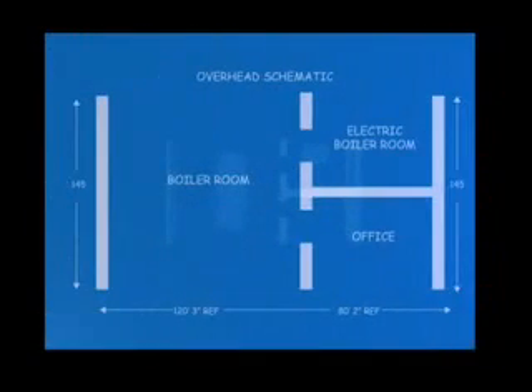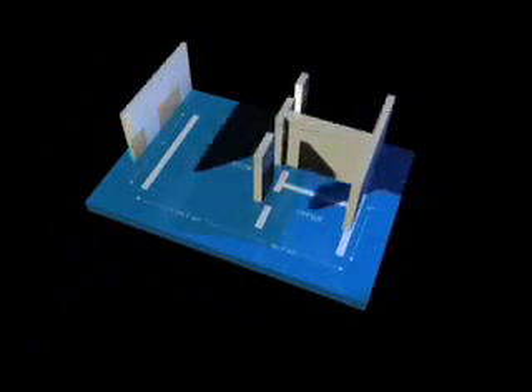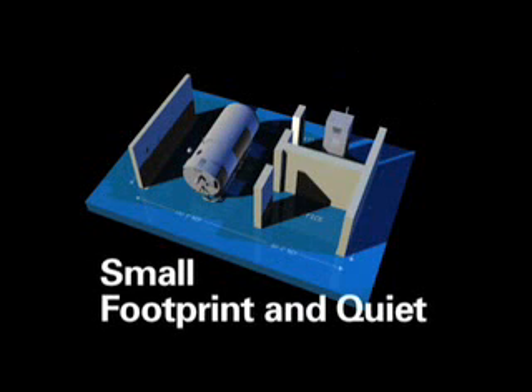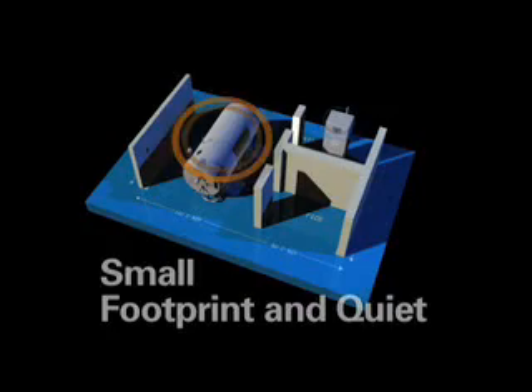Okay, but where am I going to put another boiler? Electric boilers are smaller than you think. About half the space for the same capacity. Some even fit through a standard doorway. Small footprint and a lot lighter weight. You'll be surprised where it'll fit. Electric boilers are quiet, too. No burner noise, no combustion air fans, no noisy controls. All you hear is the occasional clicking of the electrical contactors.